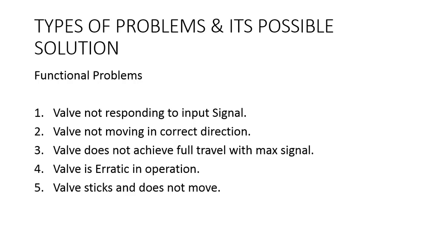Actuator action is incorrect, so we need to check the order and valve manufacturer specification. Some actuators are field reversible, so you can correct the actuator action and use that. Positioner action is incorrect, so we need to see whether the positioner is correct or not. You can rectify it very easily. Most of them are easily field reversible, and we can just check the manufacturer IOM and correct this issue.